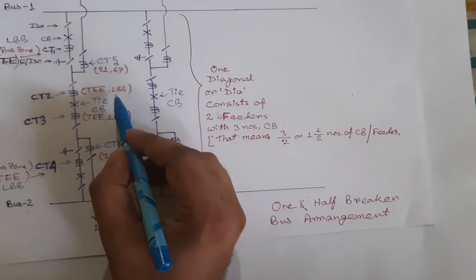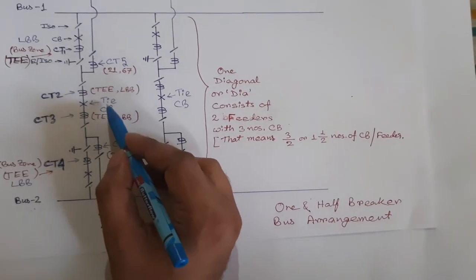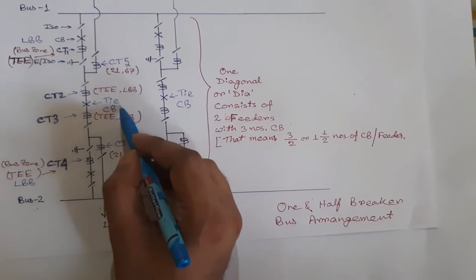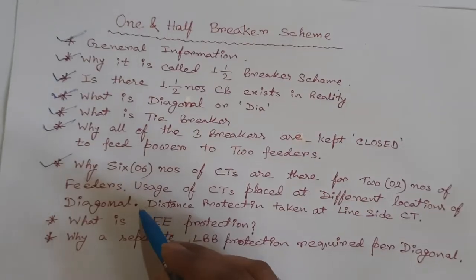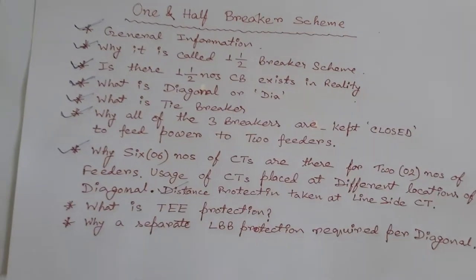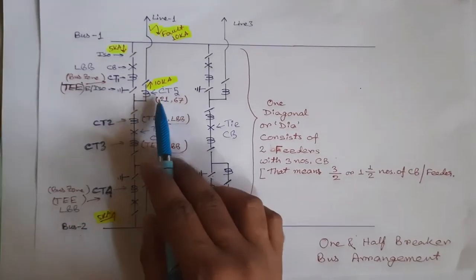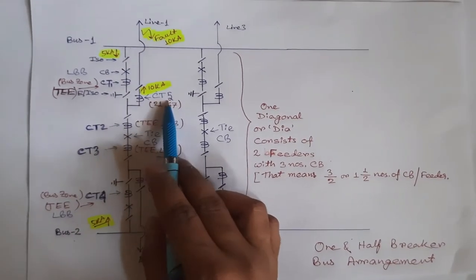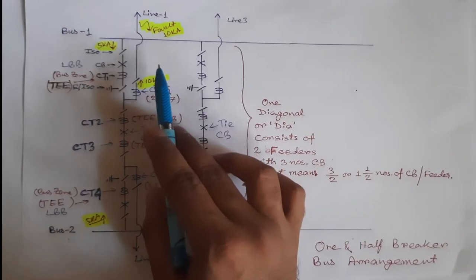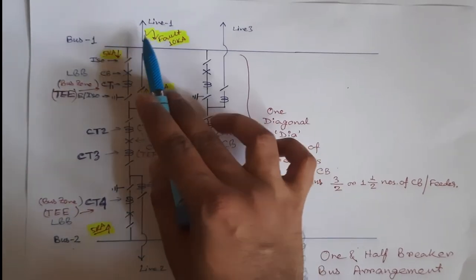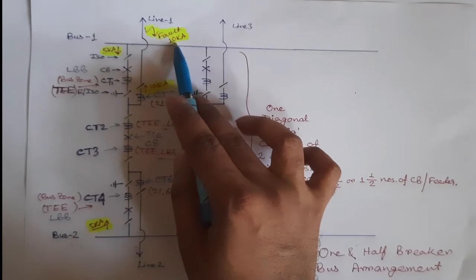This LBB is for the tie breaker. During failure of the tie circuit breaker, this tie LBB comes into picture. Now, why is distance protection taken from the line side CT? Distance protection is connected with the line side CT — CT5 in this case. To understand why, we will take a simple example. Suppose a fault occurs in line 1 and the magnitude of the fault current is 10 kilo amperes.